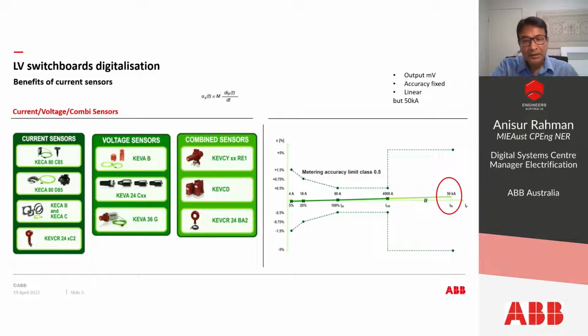And then I will move to accuracy. As you see on the right side, the accuracy is fixed, and it can be adjusted or corrected by the relay settings. And as you see, the sensor does not saturate, because its characteristic is linear. But the linearity is up to 50 kA, and that is the main challenge that we faced in the LV switchboard.